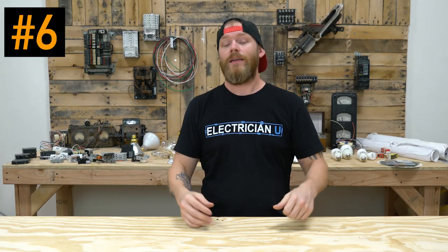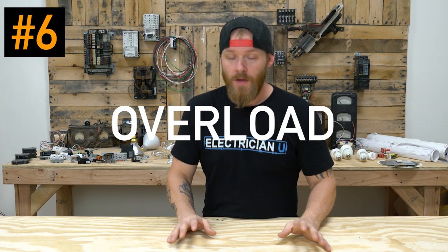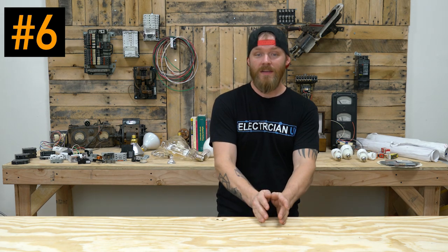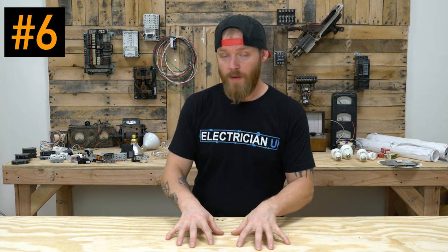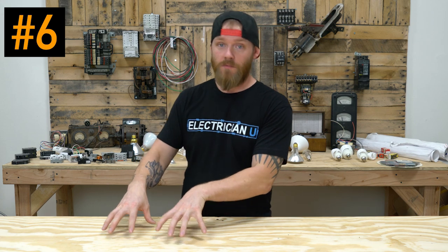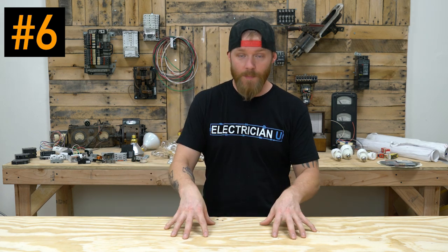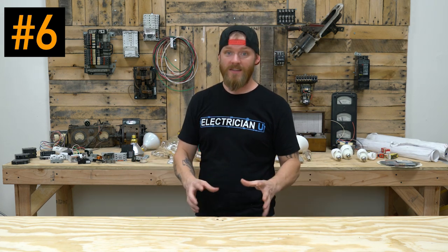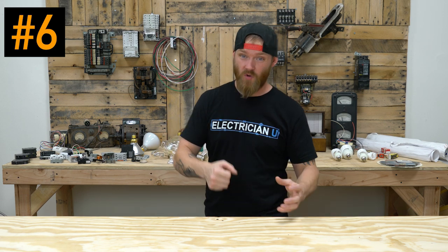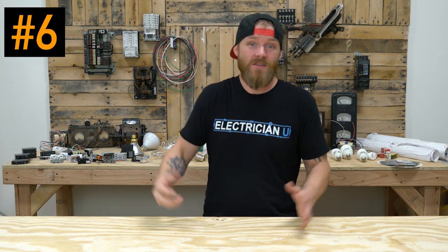Number six is an overload. Overload just means that you are using a piece of equipment in excess of its rating. So you have a 20 amp piece of equipment, and for some reason that thing is bound up and it's drawing a lot more current than it should be, and it's like running at 25 or 30 amps.